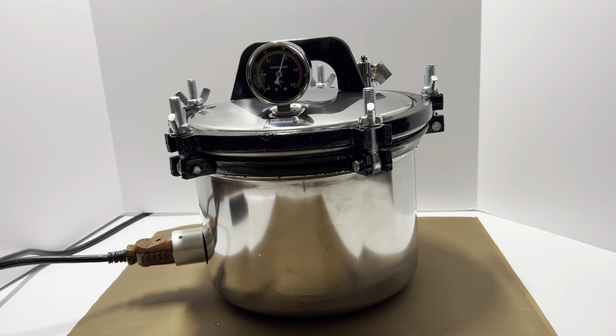And you're gonna see it's going to do that throughout the process here to keep the pressure at a steady pressure. And the temperature is going to stay at that consistent temperature as well. And the time, again, that 25, 30 minute kill time is going to be everything as well. So when we combine these elements, we combine the heat, we combine the steam combined with the pressure and time, we get a good, effective sterilization process.